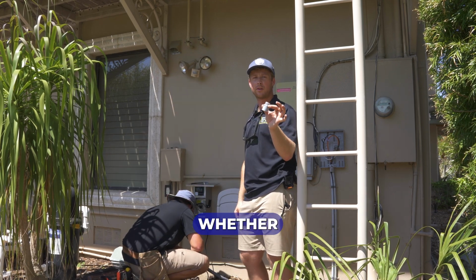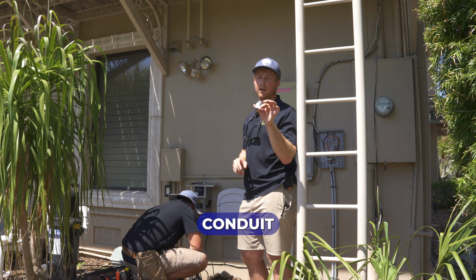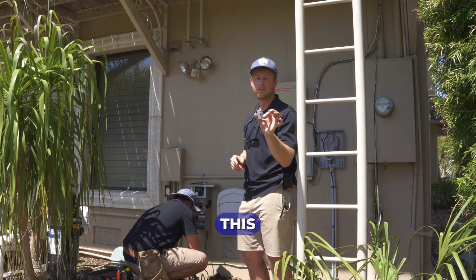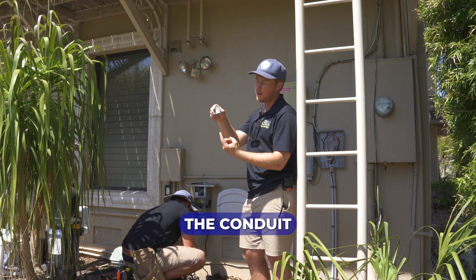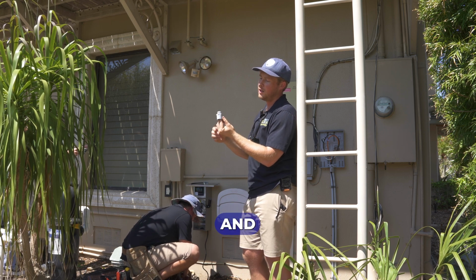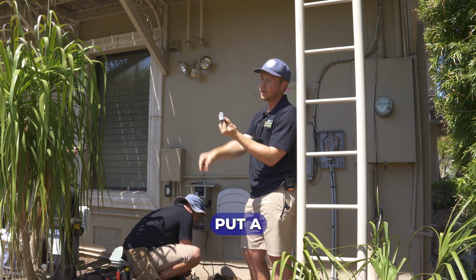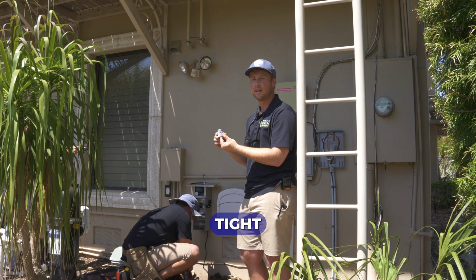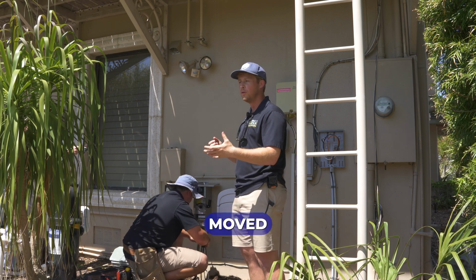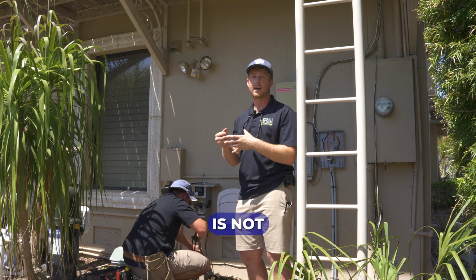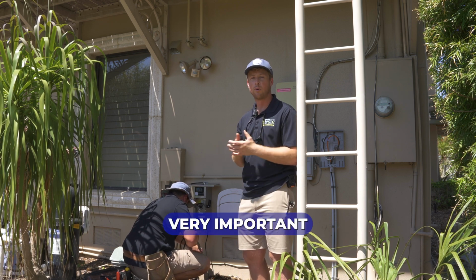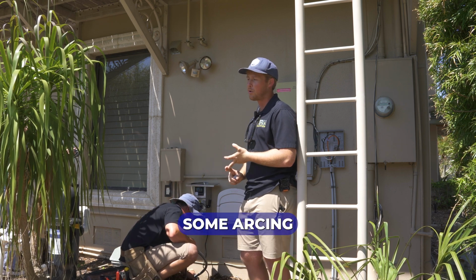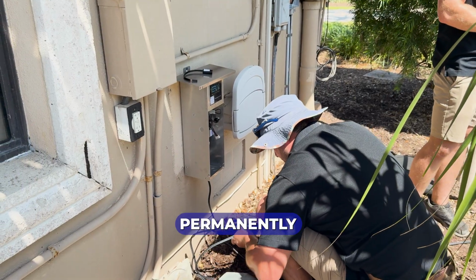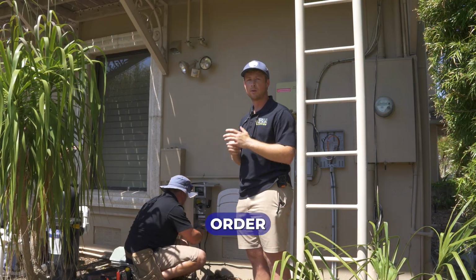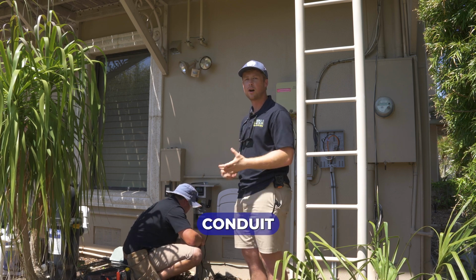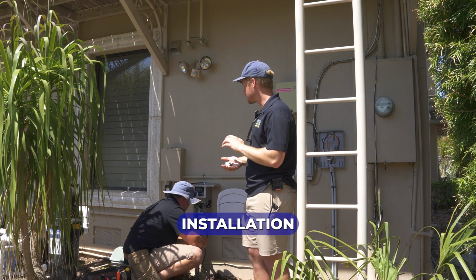These little caps, whether it's hard conduit or flex conduit, Flex has a few different ones, but we'll use this one in this case. The conduit's gonna go right up into this, and then on the inside of the transformer, we'll put a little metal ring, which is gonna hold that nice and tight. That way if the transformer gets bumped or moved or whatever, the wiring's not gonna get pulled out of the transformer, which is very important. That will cause the transformer to trip, maybe some arcing. We wanna mount this permanently, and this is an extra step that we take in order to do so. So it's really important that there's conduit used in this part of the lighting installation.